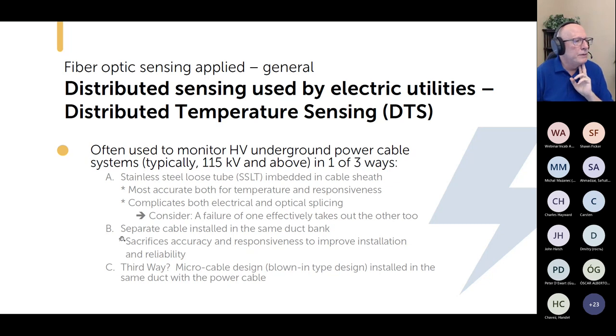What's more commonly done is to put a separate cable in the same duct bank. But here you're making a big sacrifice on accuracy and responsiveness in order to improve the installation and reliability of the system. That's a big trade-off that you're making there. So is there another way? Well, yeah, I think so. The third way. Today, there are lots of micro cable designs, particularly for blowing in. And potentially you could put a cable in with the power cable in the same duct and thereby get much better accuracy and responsiveness and much greater reliability as well.